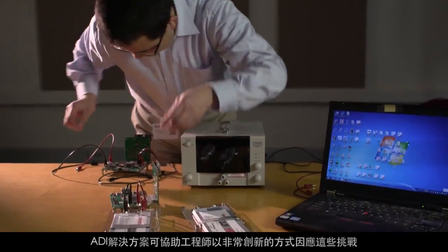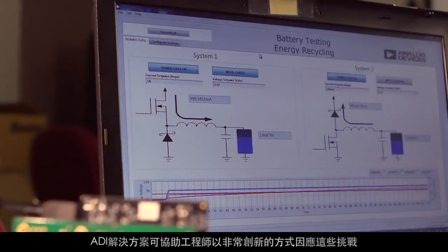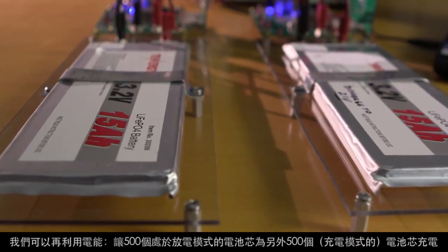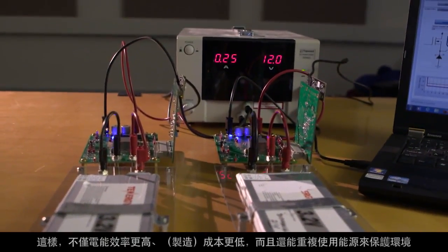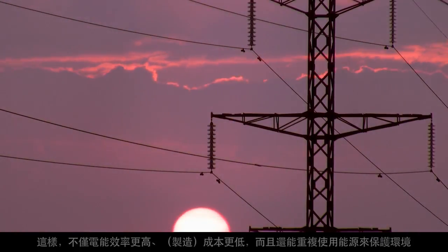The ADI solution can help engineers meet these challenges in a very innovative way. For example, with 500 battery cells in discharge mode and 500 in charging mode, we recycle the power from the 500 discharging cells to charge the other 500. This way, not only is power efficiency higher and cost lower, but we reuse that energy to protect the environment.